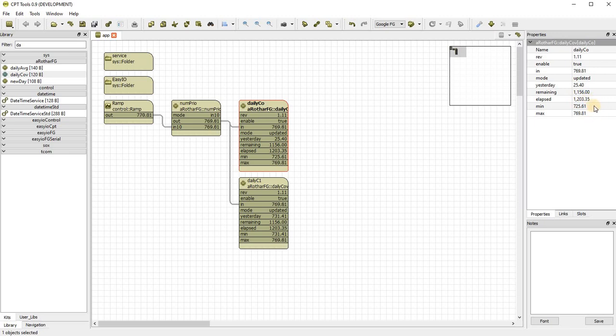The min and max shows you, the minimum shows you what it logged at when it triggered the last time. So if we trigger again, we're going to have approximately 50. 54, it'll be the same on this one. So they're very similar now, but that first blip from this bottom one is what will make the graph and the log look really weird. Also if you're carrying out queries, either SQL or BQL queries on your data, that first one will add a massive amount of inaccuracy to the values that you're producing, especially if you're looking at the whole range or on initial investigation or reporting.